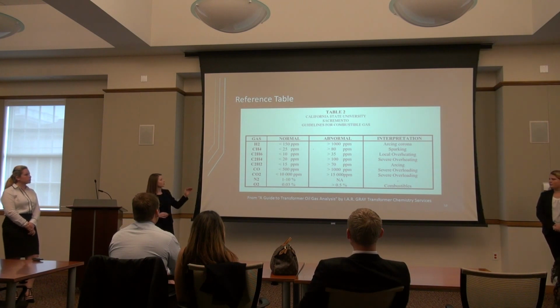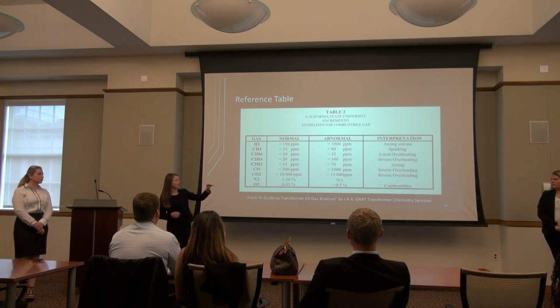So for example, the first gas up there on the top is hydrogen. So in the normal range, we want hydrogen to be under 150 ppm. If it's abnormal, that means it's over 1,000 ppm. And so if it's abnormal, then that means that arcing corona is happening within that transformer, or most probably happening.